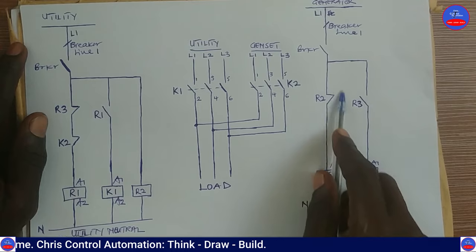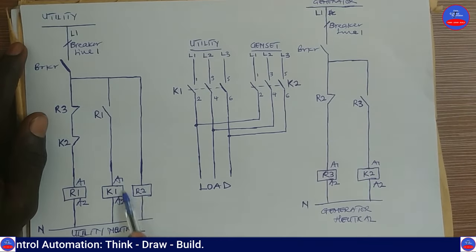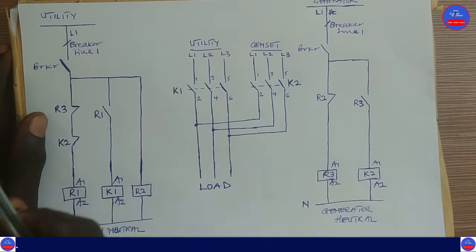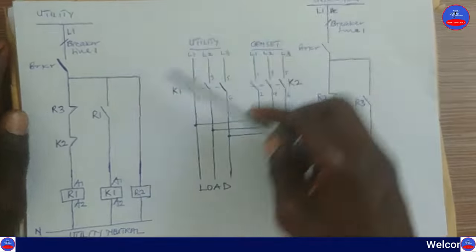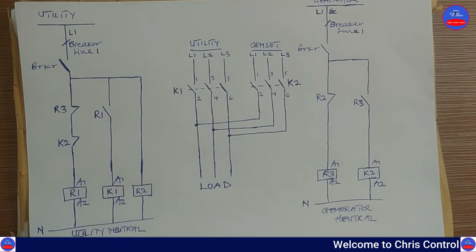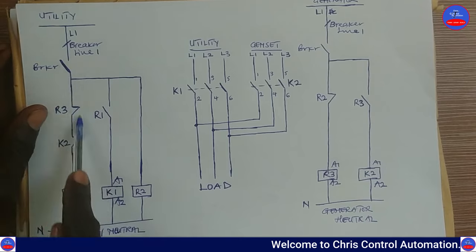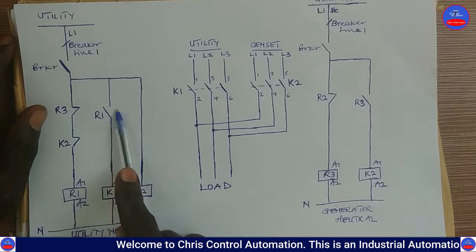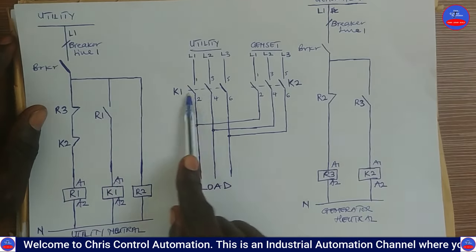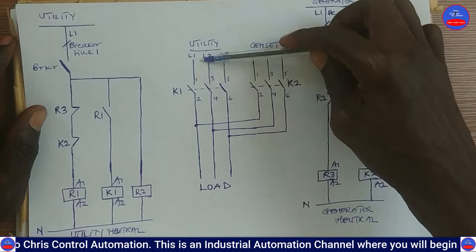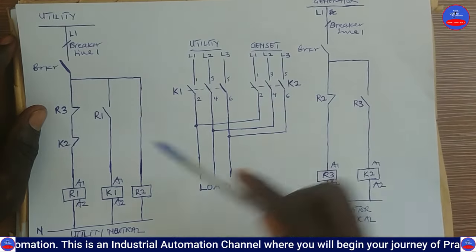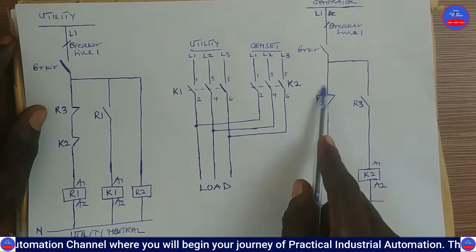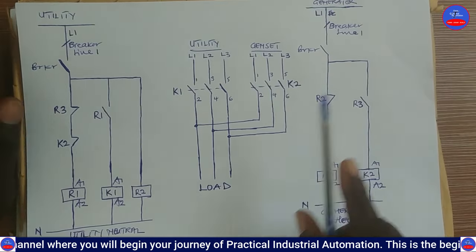R2 is serving as a sensor for the utility — I will explain that. So we close the main breaker, current flows through to energize R1, R1 closes to energize K1, K1 closes and the main utility power is applied to the load. At the same time, R2 also energizes and opens its contact on that side.